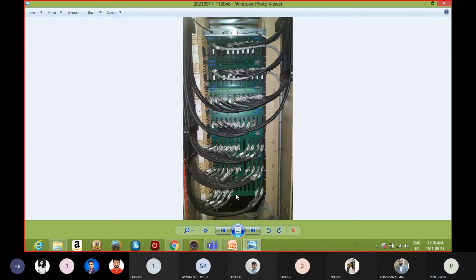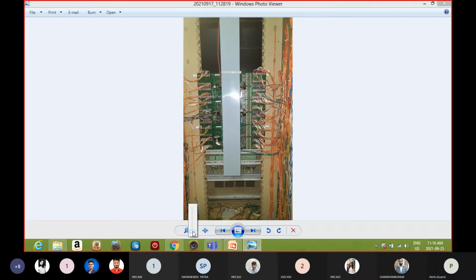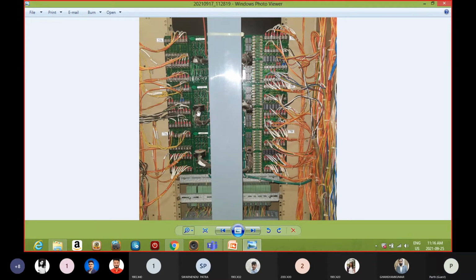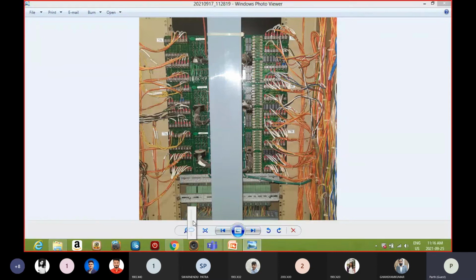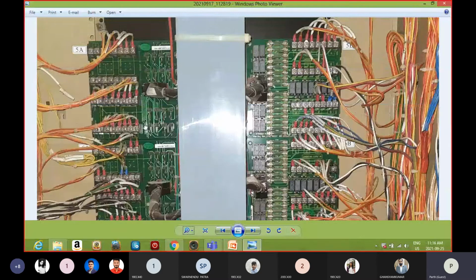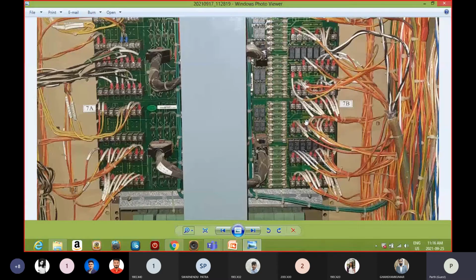Here you can see these are the different IO cards, and in each different IO card, the prefab cable goes in here. Prefab cable is coming here. This is the second panel of that module unit. I already explained that there are 3 to 4 panels in one node, one PCU. So this is the second panel. Prefab cable from controls will come here, and you can see these are the cables. These cables will directly go into the field and actuate the final control element.